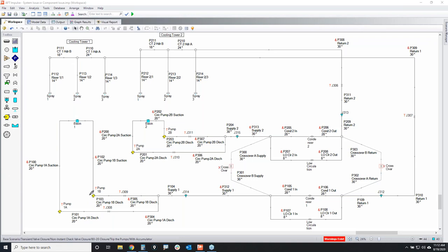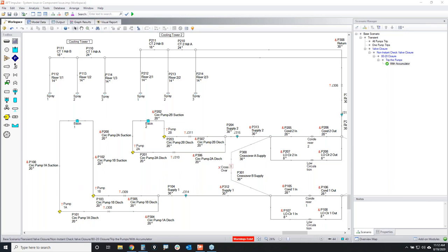And this is an example of what you might do in your particular situation, where what you know is you have a valve closure. That's your problem. That's the thing that's causing all of the other issues in your system. Start there. Start with the valve closure that you know what's going on, and then try some other things. If you have check valves, try seeing if you can allow the check valves to chatter a little bit less than instantaneously. After you go through that, try a scenario where you change the way that a valve closes. So if this is an emergency failure operation, you don't want that valve to close fast or linearly. So maybe try a different way to close the valve. That way can help maybe dampen out those surges. It's not a good thing to allow your pumps to deadhead against closed valves, so you might want to consider doing a pump trip as well.